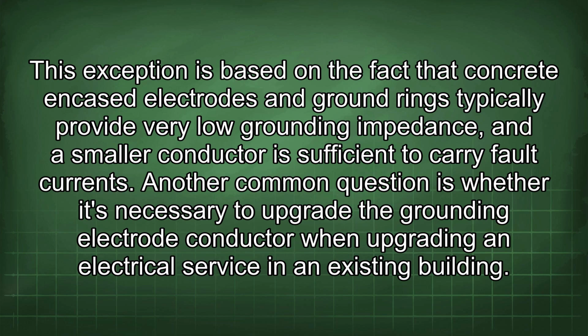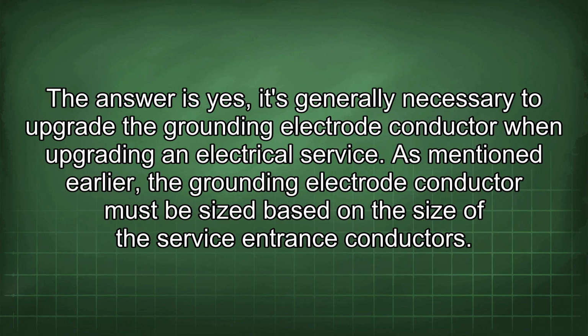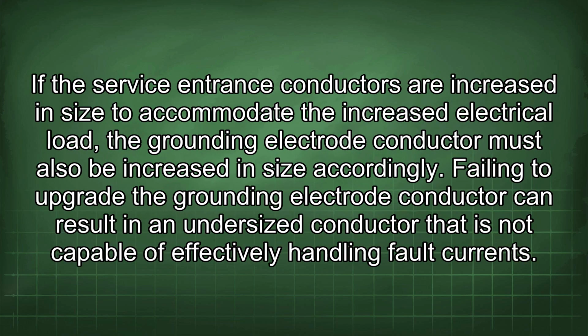Another common question is whether it's necessary to upgrade the grounding electrode conductor when upgrading an electrical service in an existing building. The answer is yes, it's generally necessary to upgrade the grounding electrode conductor when upgrading an electrical service. As mentioned earlier, the grounding electrode conductor must be sized based on the size of the service entrance conductors. If the service entrance conductors are increased in size to accommodate the increased electrical load, the grounding electrode conductor must also be increased in size accordingly. Failing to upgrade the grounding electrode conductor can result in an undersized conductor that is not capable of effectively handling fault currents.